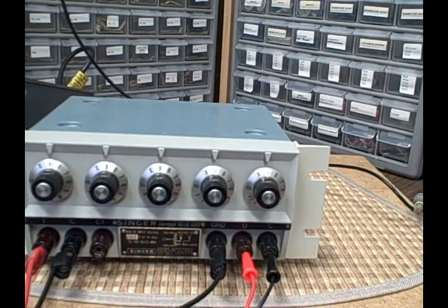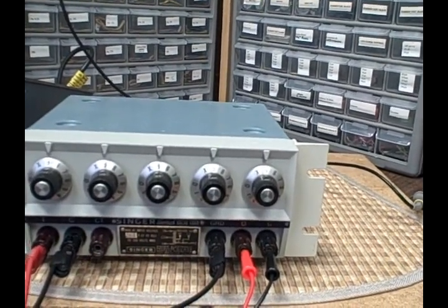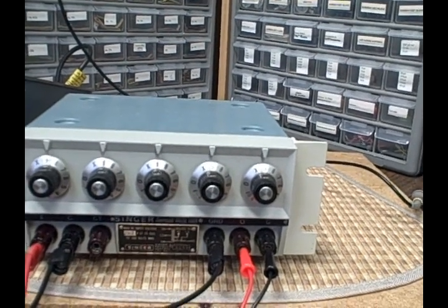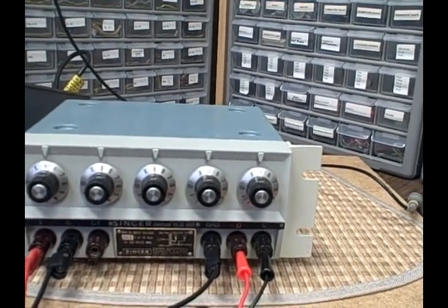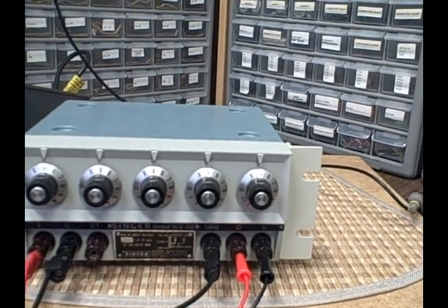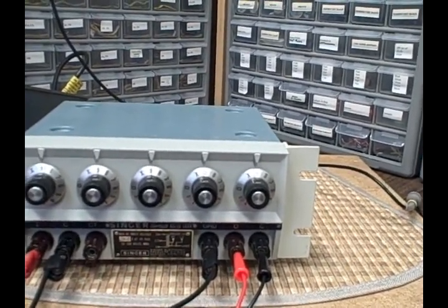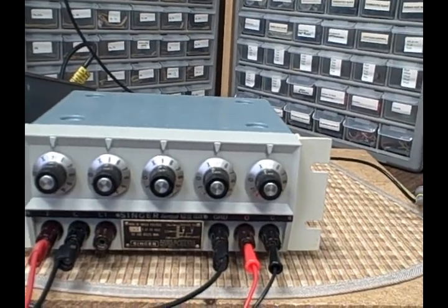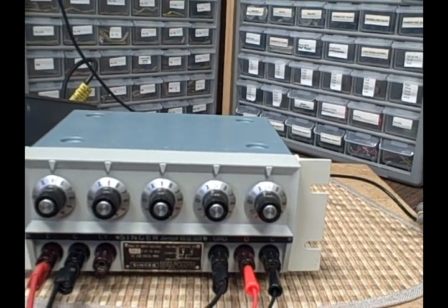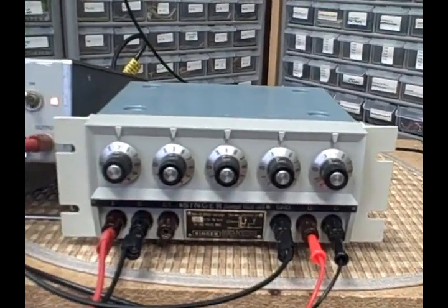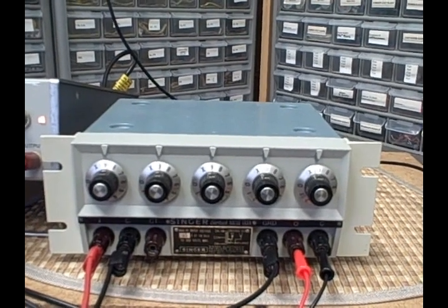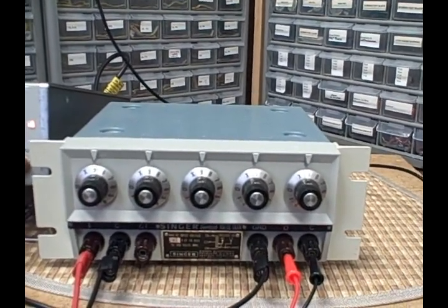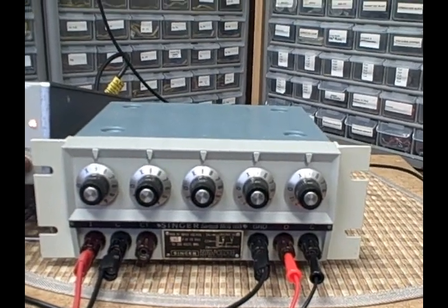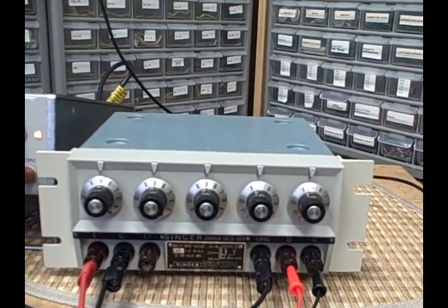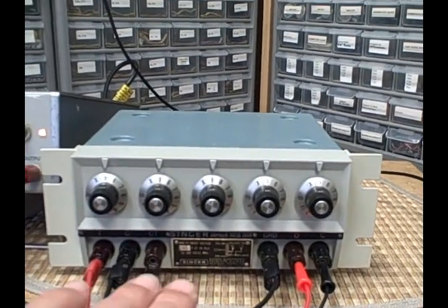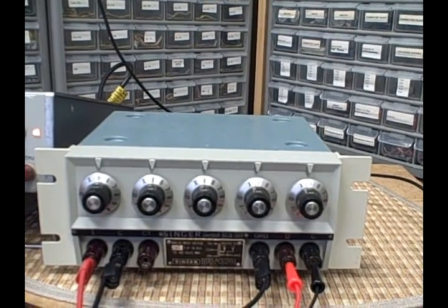Now, if I wanted to go beyond 1,000, let's say I want to go up to 10,000, that's a factor of 10 times more. That means my voltage, my 350 volts, has to be reduced by a factor of 10. So we get down to 35. I'm working with 0 to 10 here, so it doesn't matter to me. At 10,000 hertz, I'd be good at 10 volts. It's less than a third of the 35 volt maximum. Anyway, that's one of the disclaimers and things you have to worry about on the ratio transformer.